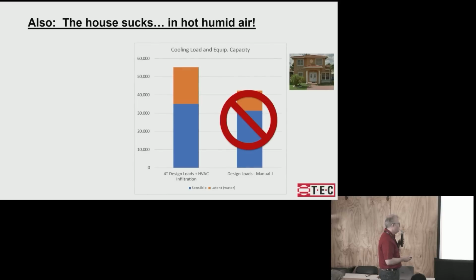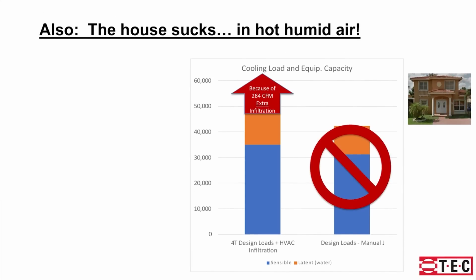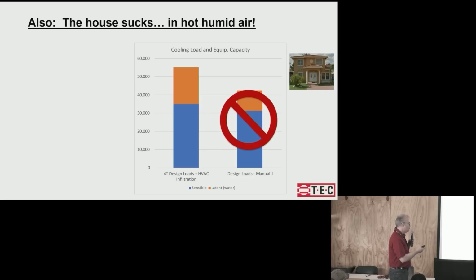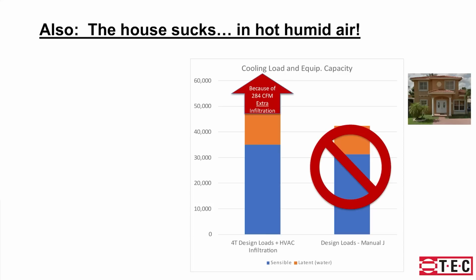So we don't have these loads anymore. We actually have these loads. The load is increased because we're sucking in more air than we thought we were. So this is a double whammy. Not only do you lose capacity out the attic, but you also add load to the house because you're sucking in hot air. Yes, so sensible went up, but look what happened to the latent. The latent is crazy now. It's like more than doubled.